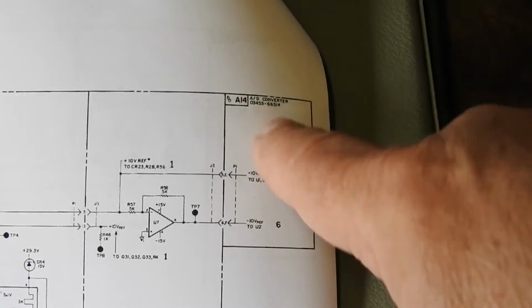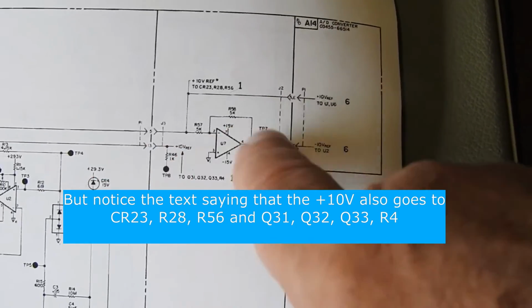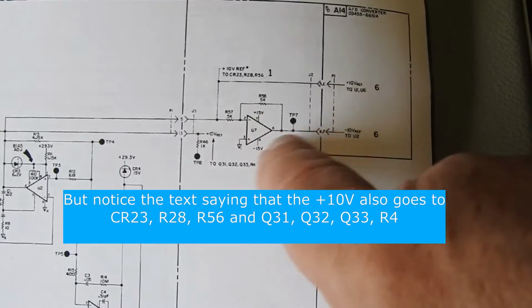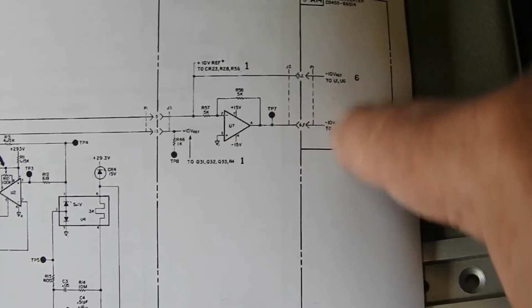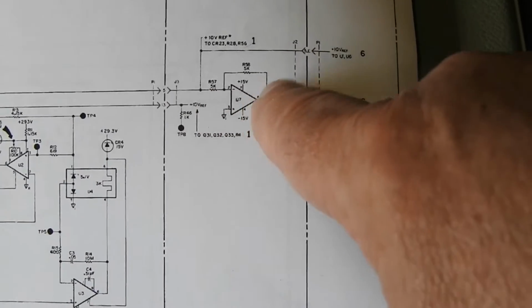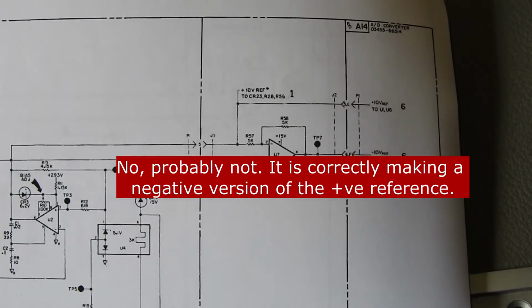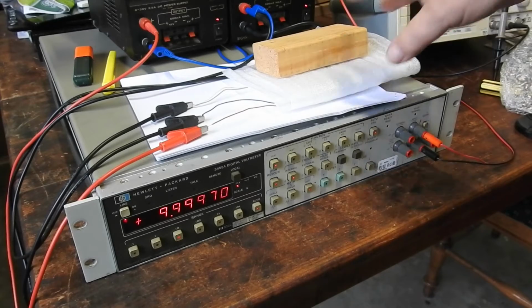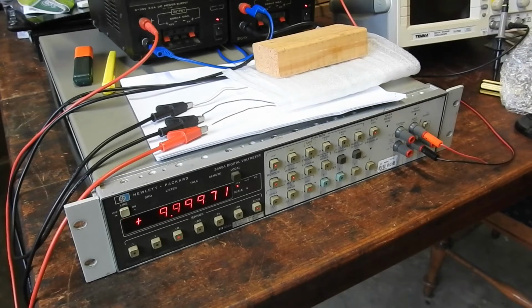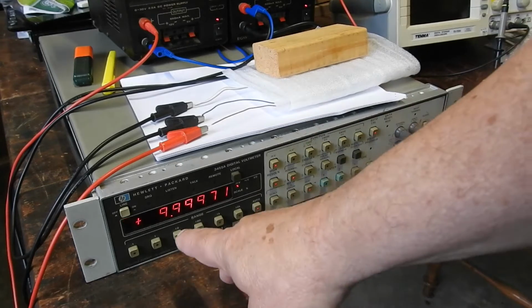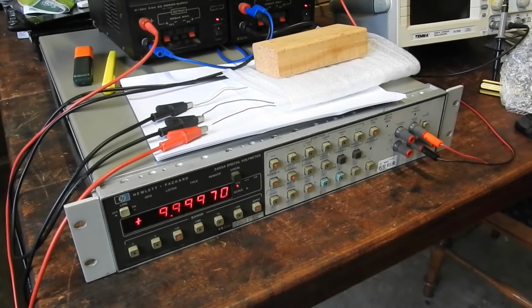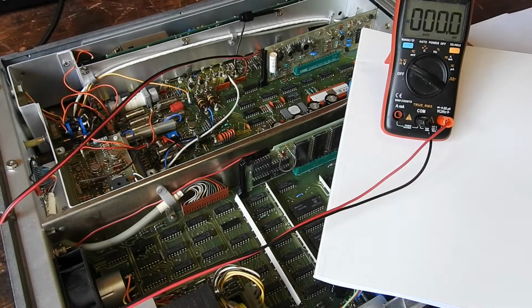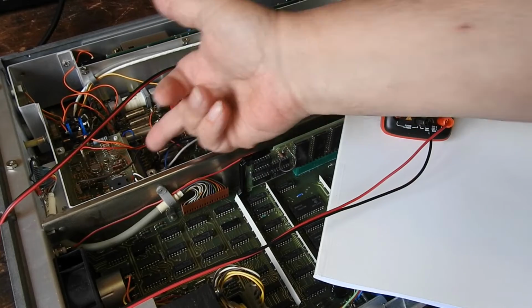It goes to this inverter and then to the A to D, and these are the 2 points we measured before, which were wobbling and only 7.6, so it looks like when we disconnected that and they were still bad, although they weren't jumping as much, they were still about 7 volts though, so it looks like there's something wrong around there. Hopefully that's easily fixed. I'll put the reference in a bit of thermal insulation to try and let it stabilise, and it's been running for many hours, and it's drifted down. It seems to have levelled off at 9.9997 volts.